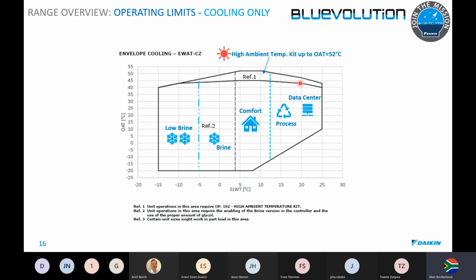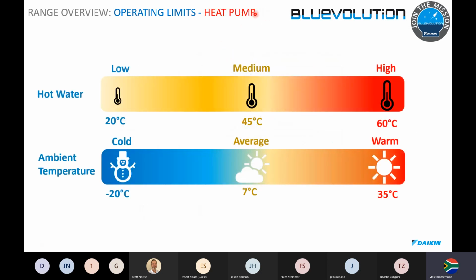But here, typically, you can see chilled water temperatures for ideal situations. Pretty much comfort cooling, we leave in about the 4 to about 13 degree range, supply and return water temperature, and up to 25 degree return water for data centers. We don't want to supply too cold water to data centers because you're going to get too much condensation on the lines, and you don't want to dehumidify the air too much in a data center. So we don't make the chilled water too cold, else you're going to create high static electricity, which we want to avoid. We also provide the heat pump version, so we can generate hot water for you as a byproduct of the cooling operation.